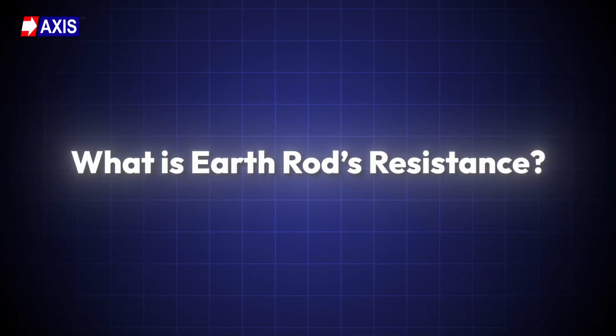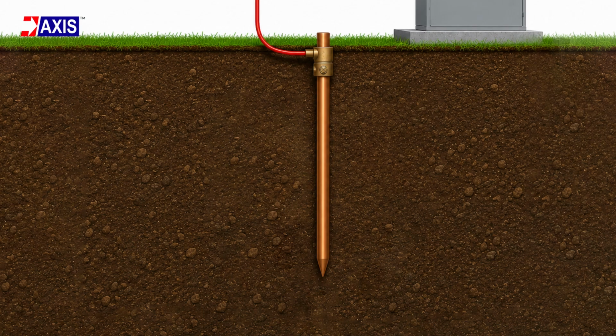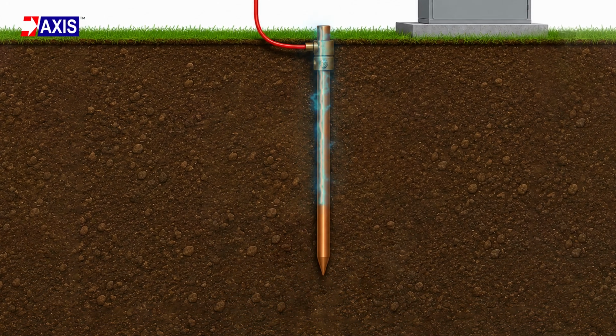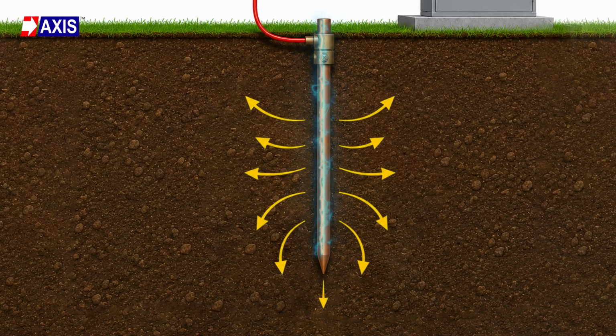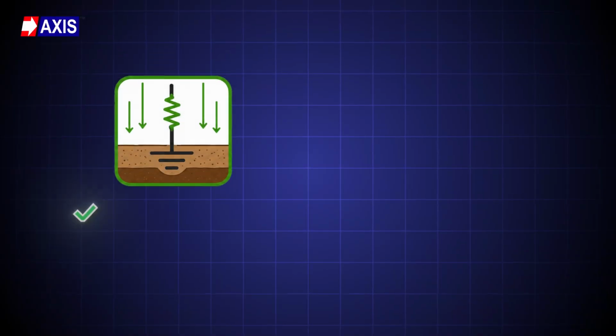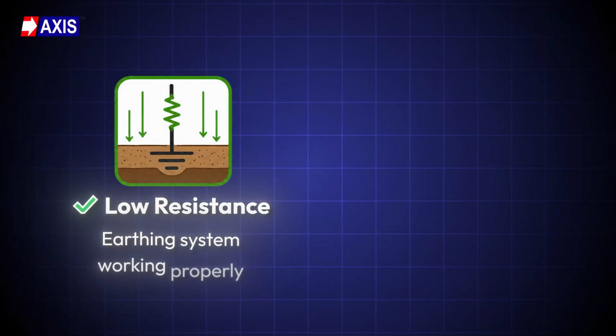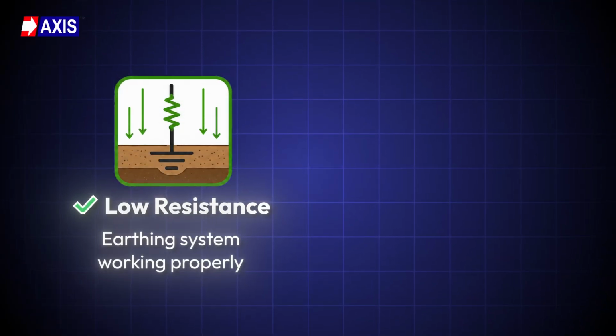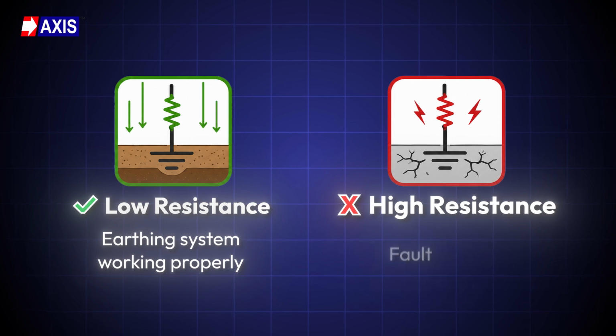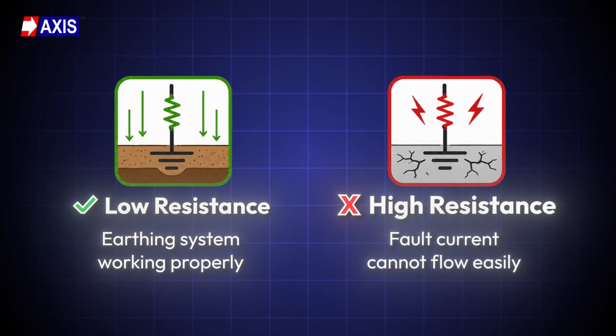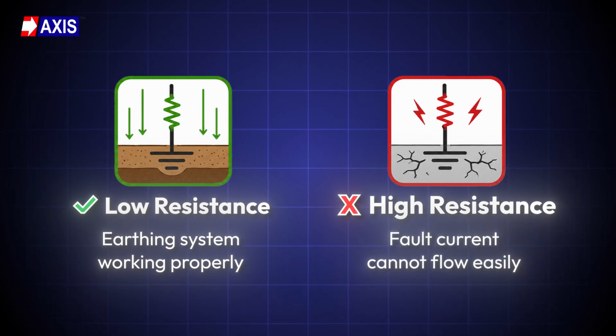Let's start with the basics. Earth resistance is measured to check how easily fault current can flow from the earthing system into the surrounding soil. A low resistance means the earthing system is working properly. A high resistance means fault current cannot flow easily from the earthing system, which creates a safety risk.